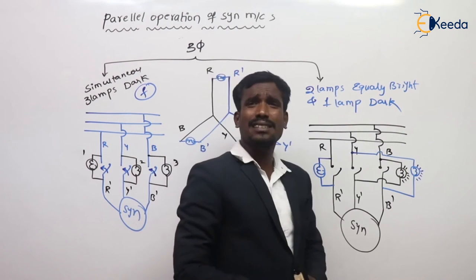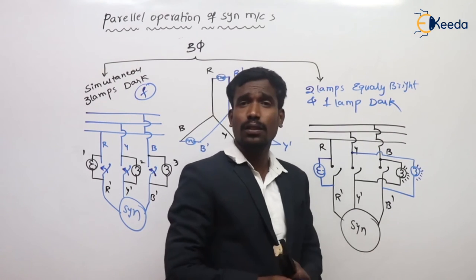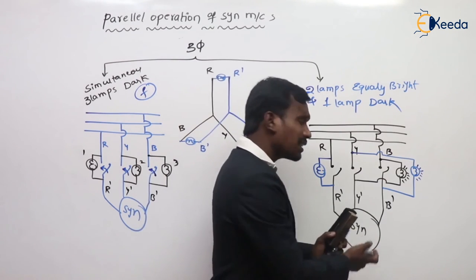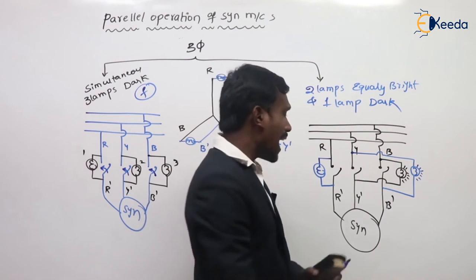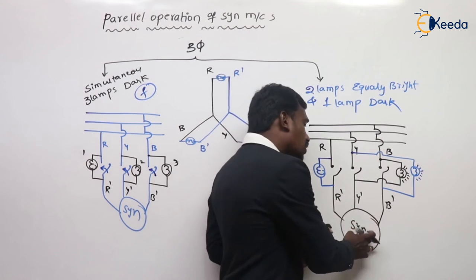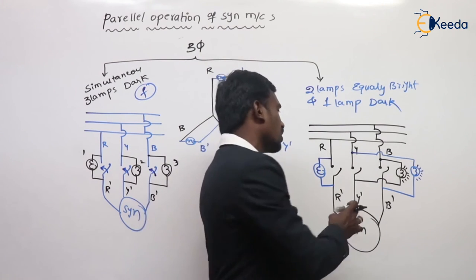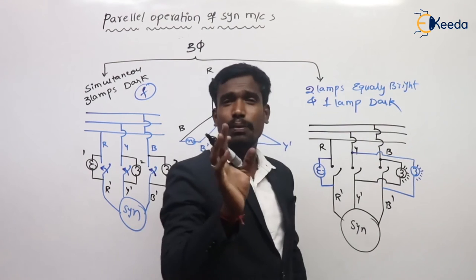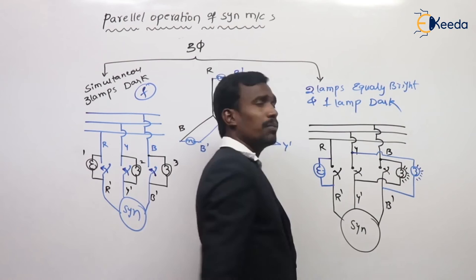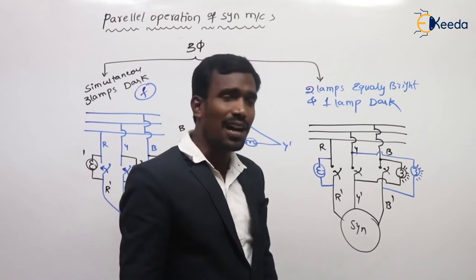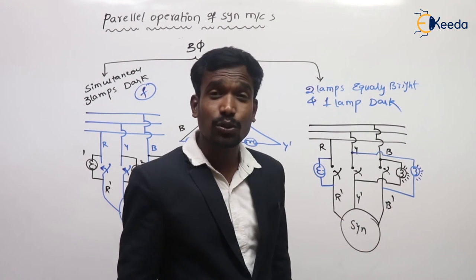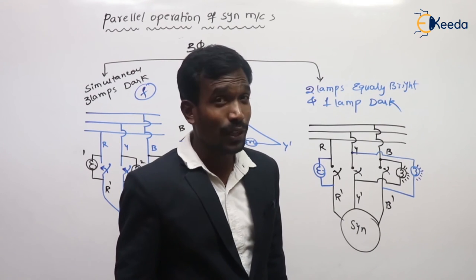If the phase sequence is not same, we have to make it same. If the frequency is not matched, we have to change the speed of our synchronous machine. By changing the speed, or by changing the excitation, the two frequencies should be matched. When the frequency is matched, the two lamps give bright and one lamp gives dark — then we close the switch.